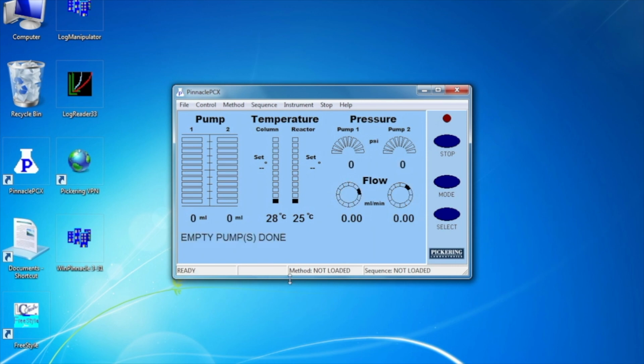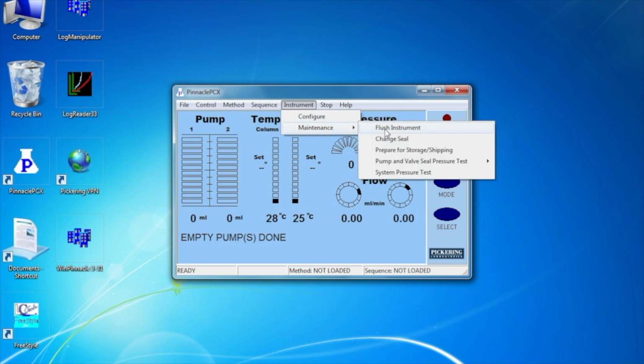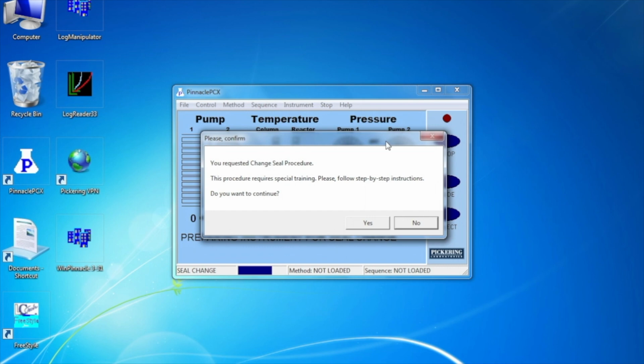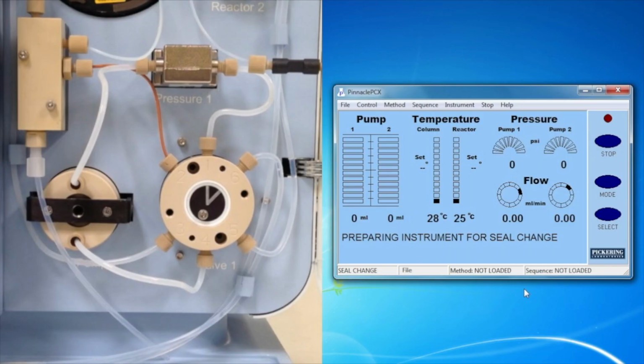Once the pumps are empty, prepare the Pinnacle for a seal change by selecting Change Seal in the Maintenance section of the Instrument drop-down menu. Make sure to follow the on-screen instructions for the Pinnacle control software. The Pinnacle will now flush out the pumps with flush solution from port 5 of the valve.